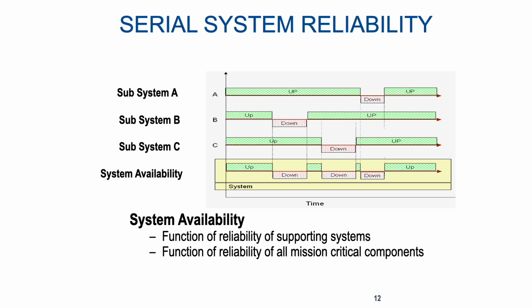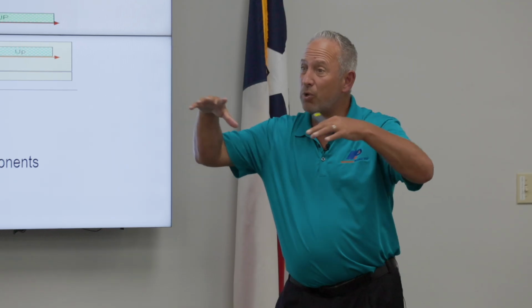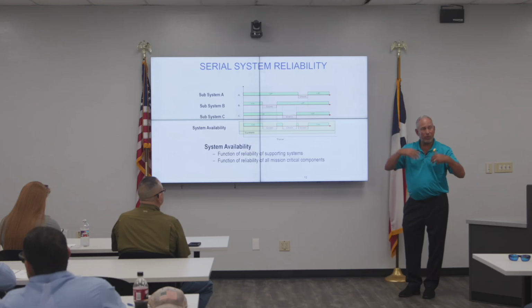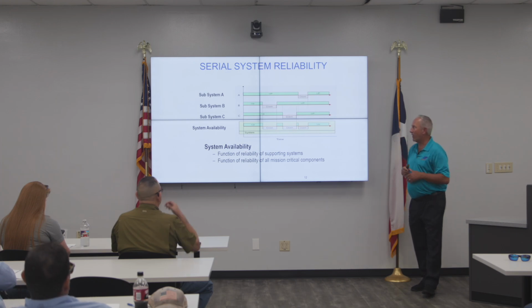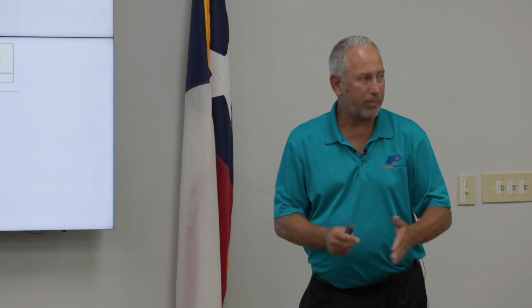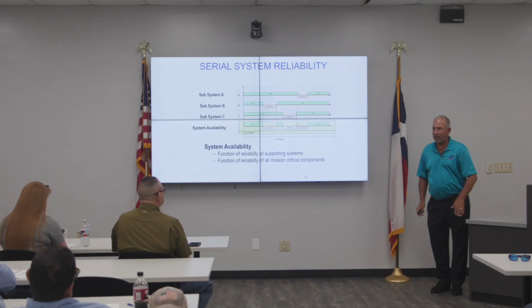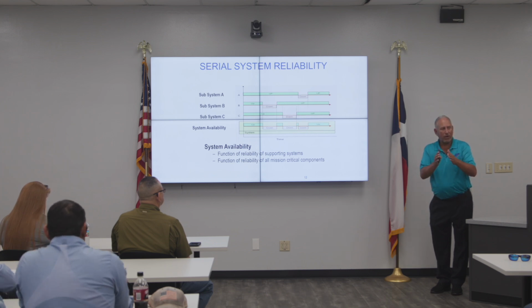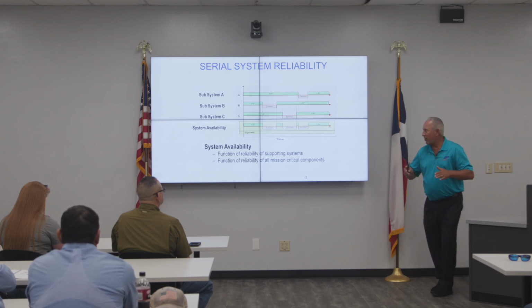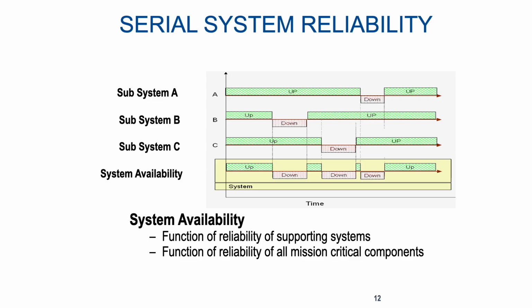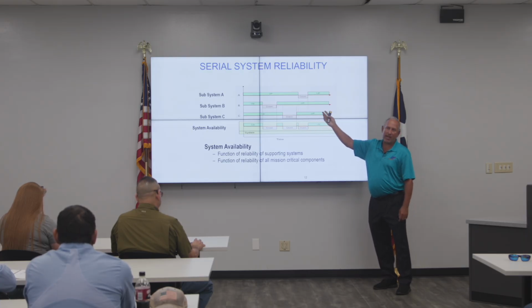This is an easy way to get your head around it. Generators are basically a series of subsystems - you've got an engine, an alternator or generator on the back end, and controls. Those three pieces together are what make the gen set operate. Looking at it as subsystems gives you an idea when it comes to reliability. If you've got an engine issue, you're down for that long, but that's fine, you're just down because of that one subsystem. But if you get a subsystem failure once a year on a different subsystem, your overall reliability is going to be affected. You won't feel it during that time, but you'll feel it at the end of the year, because if you lose your control system, the generator's not going to work. So paying attention to each one of these subsystems is the key to reliability when it comes to the genset.